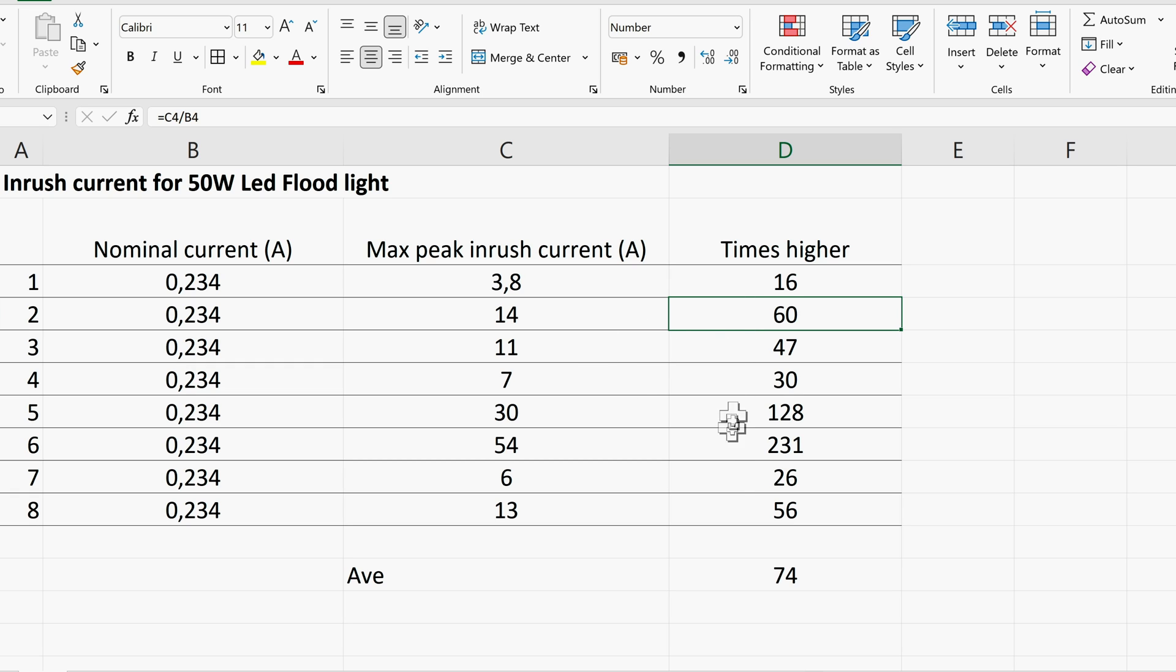And if you scroll down the list one can see that sometimes the inrush current is way above a hundred times higher than the nominal current. So I have seen reports on the internet saying that LED turn on current can be more than a hundred times higher. And I was a bit skeptical of that. But now having tested that myself I can see that even 200 times. And as I said, this really does depend on the LED driver circuit and at what phase the voltage was at the time of turn on.